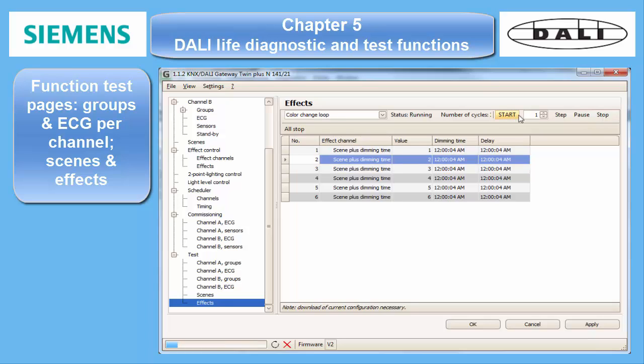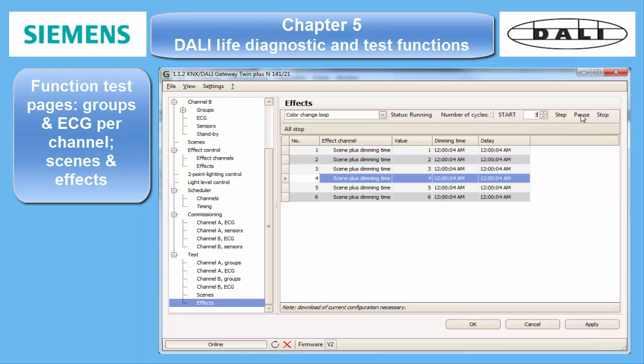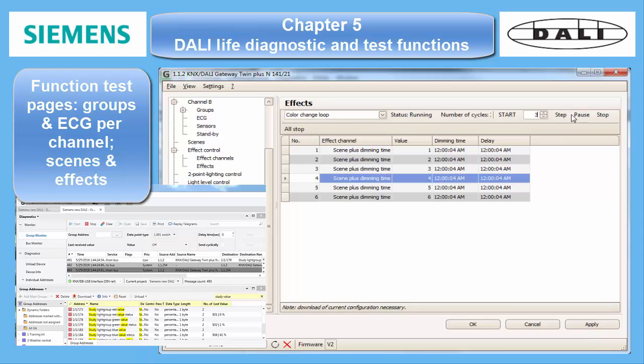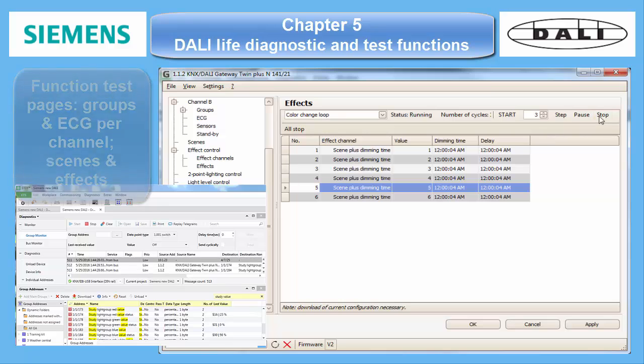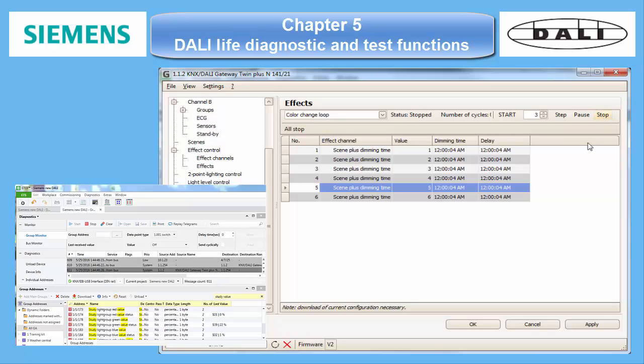In the list below you can see some strange timer values. This is only a localization bug — you can ignore the 12AM here. By the way, the effects are the only function where the DALI gateway sends KNX telegrams. The reason is that the effect control only works via the KNX bus.